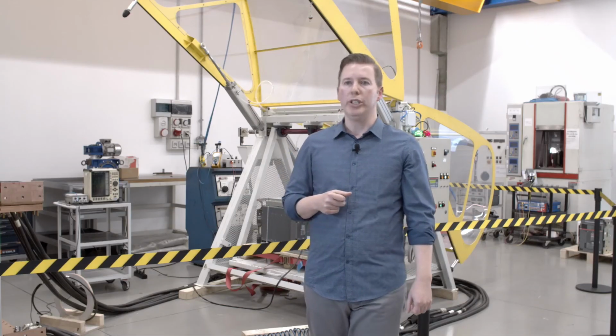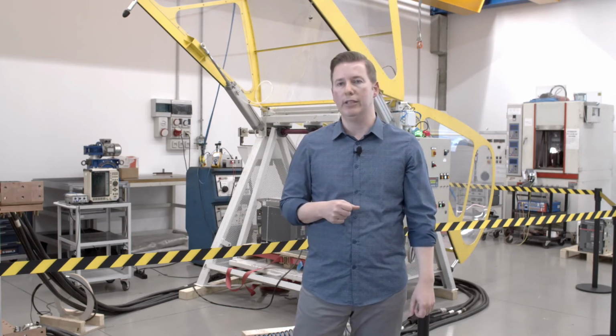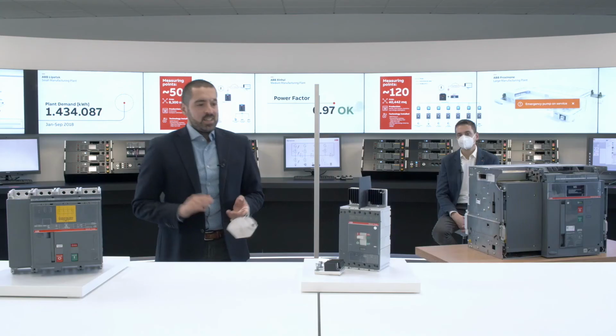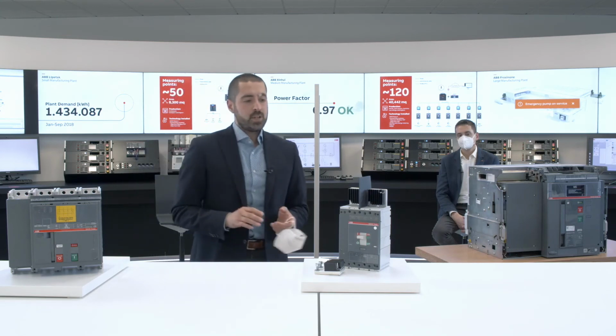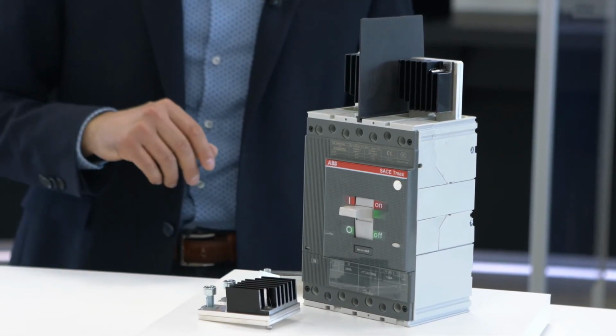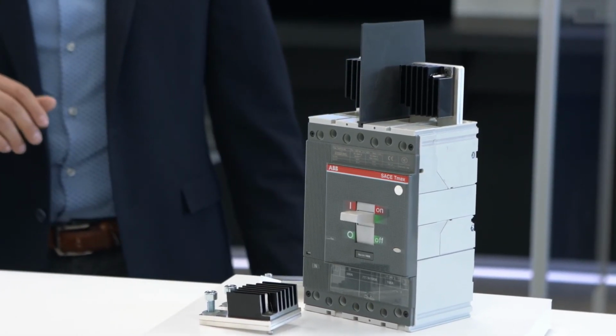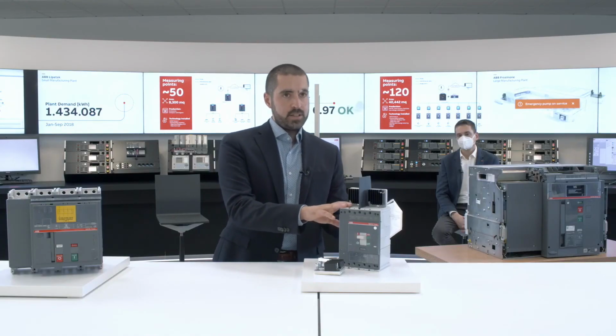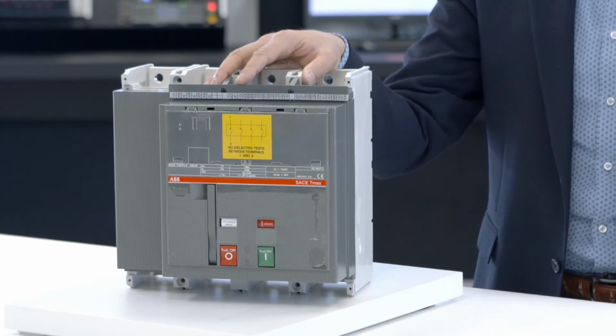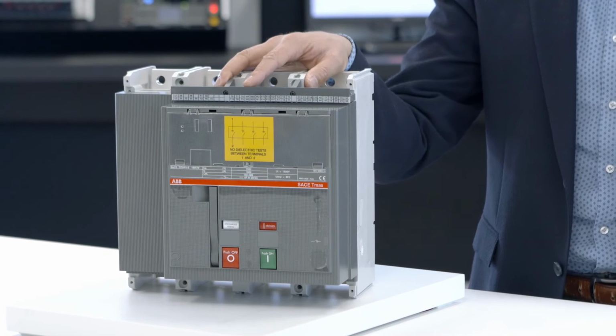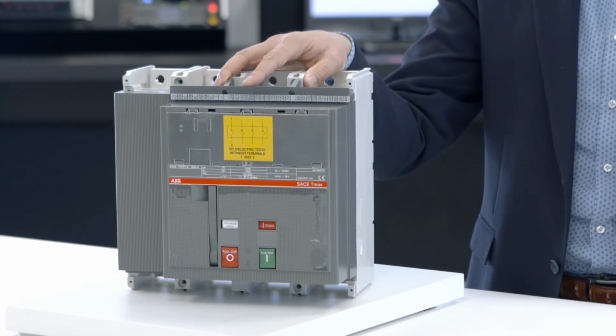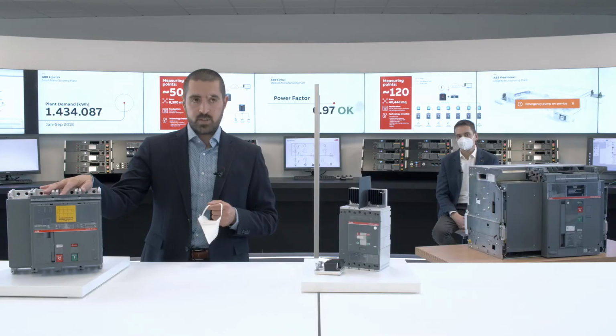Thank you. And which product are UL certified for DC applications? For ACBs, we develop our solution in UL 489B for photovoltaic and the UL 489F for energy storage systems. With MCCB offer, we can cover application up to 1,500 volt DC, up to 200 amps, according to UL 489F and B, with the T4 circuit breaker for DC application. And for the switch disconnector, we can cover application up to 1200 amps at 1000 volt DC, according to UL 489B, with the T7 switch disconnector.